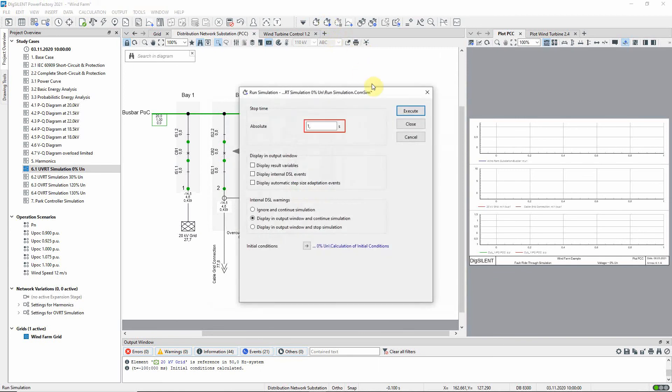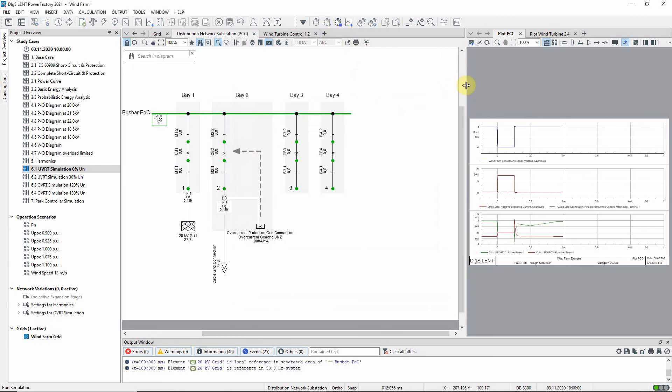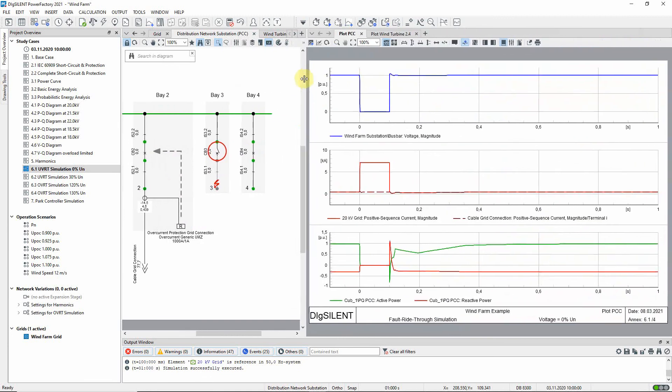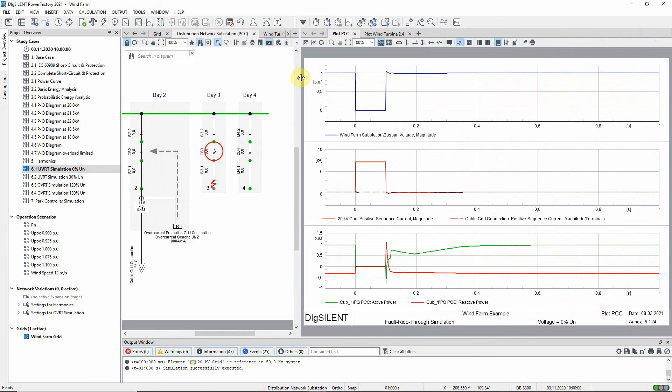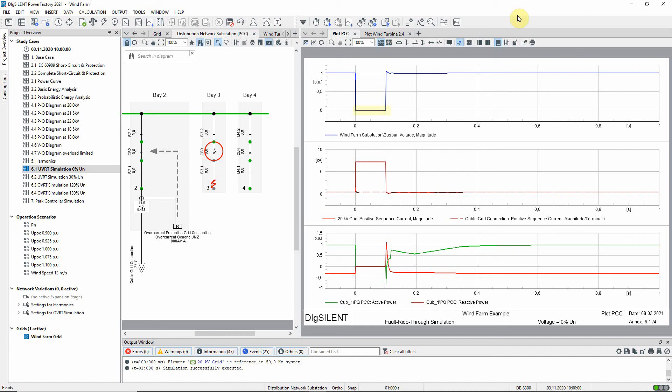Run the simulation for one second, and have a look at the plot PCC page. The three plots show the variation of various parameters with respect to the simulation time. The top plot shows the voltage at the busbar of the wind farm substation. It can be seen that when the short circuit is applied at zero seconds, the voltage at this busbar reduces to zero. It stays at zero until the fault is cleared at a hundred milliseconds. At this point, the voltage rises back to its pre-fault value.